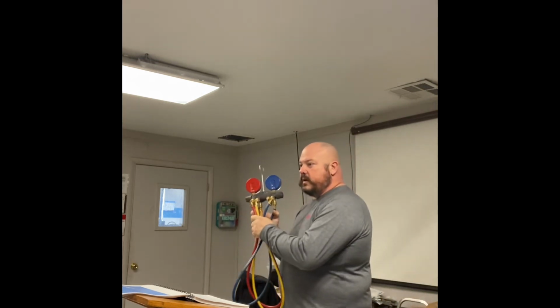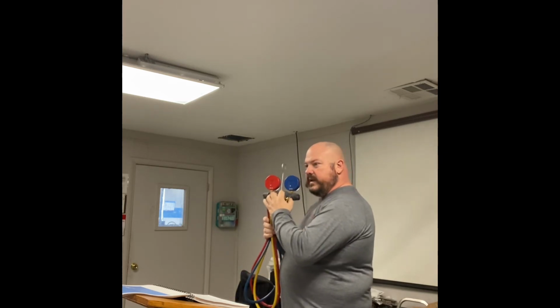Number two is non-condensables in the system. This is that service technician that has dirty equipment. I know that people are going to tell you it's bad to vent off the stuff in your gauges. Well, I don't want to put the possible contaminants from one system into the other. Number two, I want to keep everything pressurized in my gauges until I get to the next one, so it doesn't have a contaminant in it. Okay? Where did I go through the gauges? Over there. You don't want your hoses dragging through the mud. You do not want water and stuff getting inside of here.